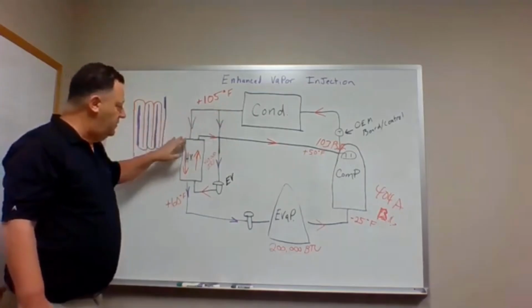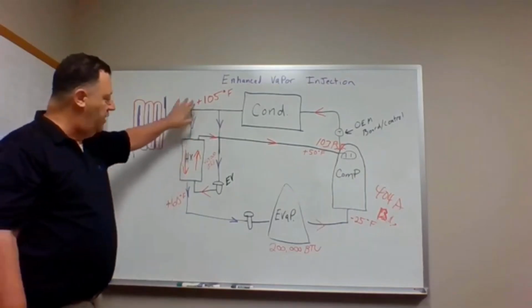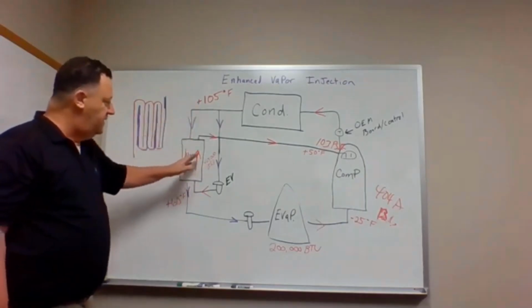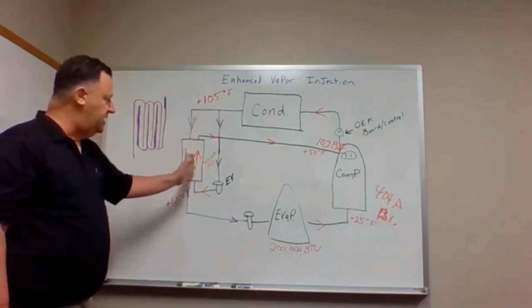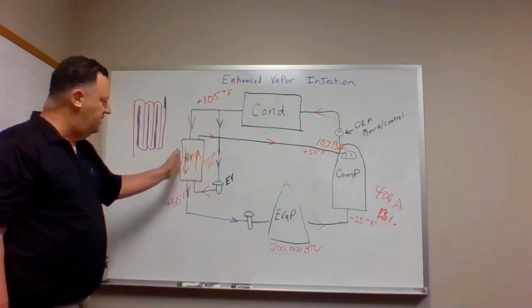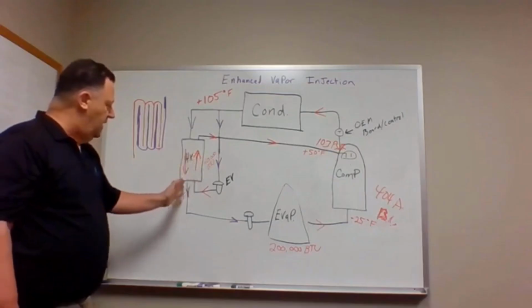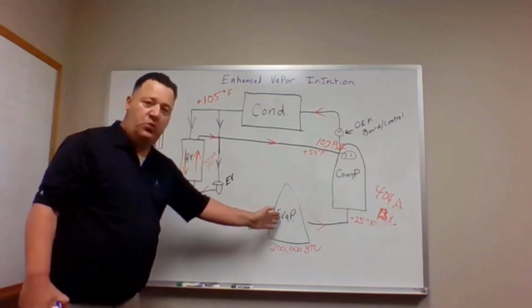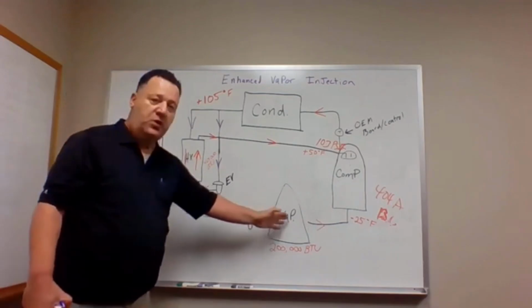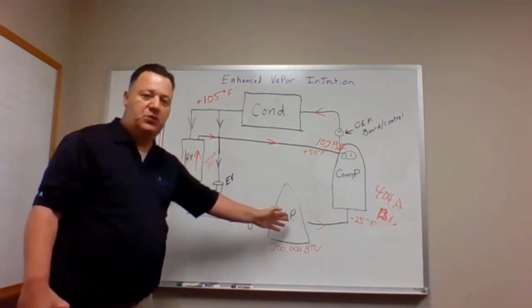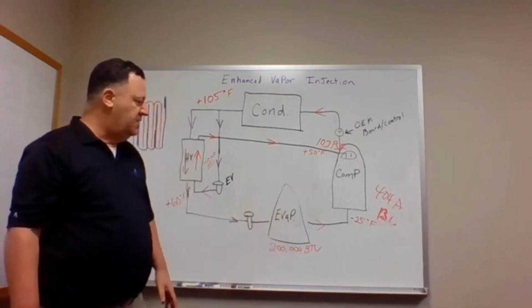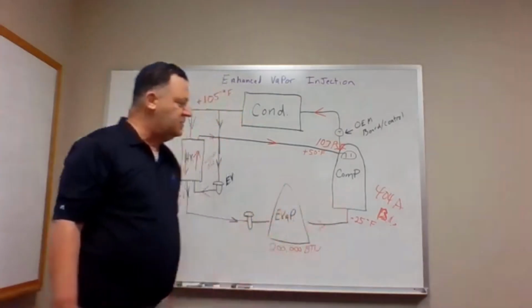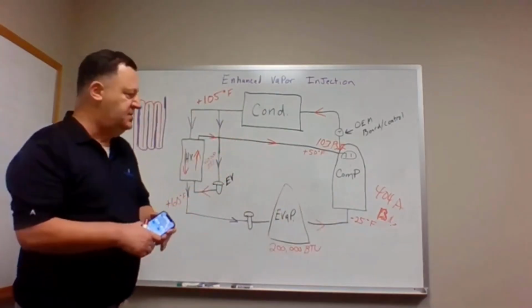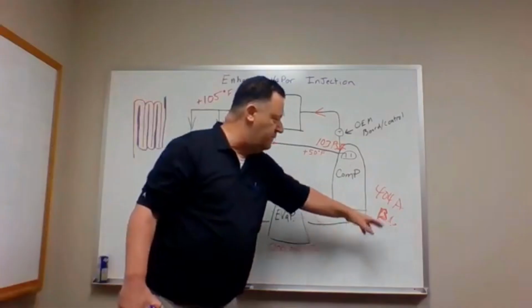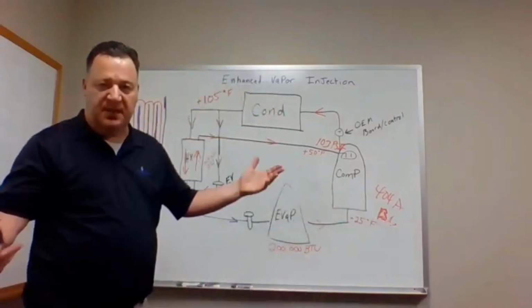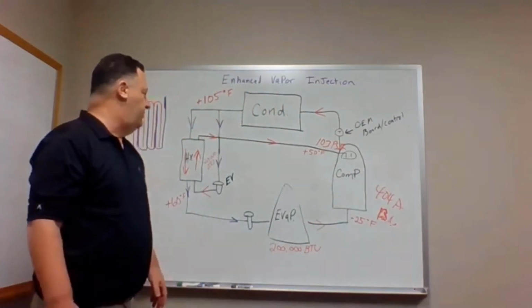So I've got liquid coming through the heat exchanger at 105. I'm removing some of that heat. Again, this is a heat exchanger. Think of the right side as an evaporator, the left-hand side as a condenser. I removed 45 degrees. That's a win-win, okay, because we're getting more capacity out of that, the more subcooled liquid we have, all right? Still going in at minus 25, we're saying, and I just threw out 404A as an example. At minus 25, that pressure is 13 point something, 13.2 or somewhere thereabouts.